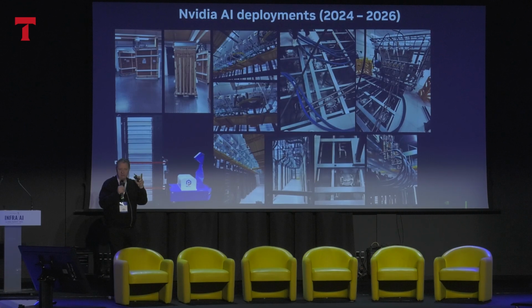If you have an average air-cooled rack of, let's say, 25 kilowatt, this rack is approximately 500 to 600 kilos. This rack is 1,600 kilo, and Vera Rubin, which is coming end of Q3 this year, is 2,000 kilo. Going further, a normal 48U rack, 600 by 1200, that metal frame is good for 4,000 kilo. That's your maximum. The metal cannot hold more than 4,000 kilo. I hope that is not going to come, but these racks are right now up to 2,000 kilo.